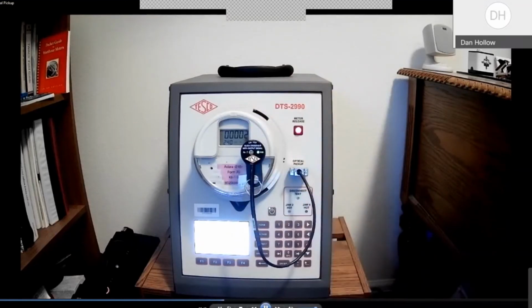In this case, the infrared test pulse is output through the optical port on this particular meter. On some meters, it's located in other places other than the optical port itself. It can be at the 12 o'clock position, the 9 o'clock position, the 3 o'clock position, dependent on the meter manufacturer type and where they've located their IR test pulse.